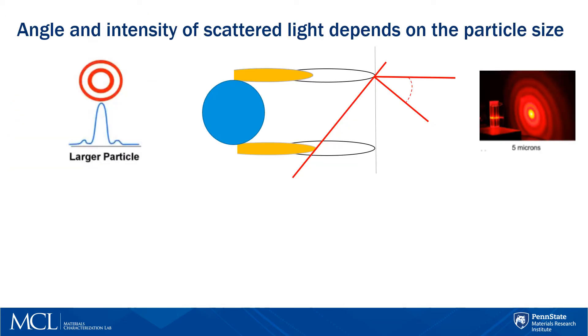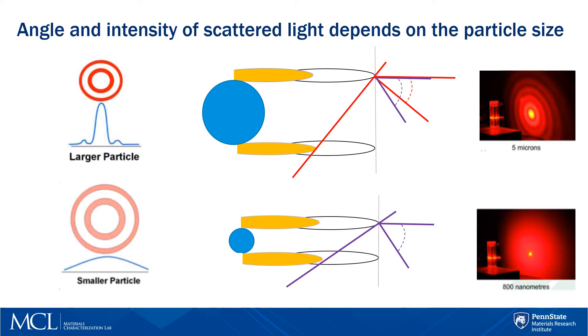We can do this because the angle and intensity of light depends on particle size. Larger particles scatter at more narrow angles but scatter light much more intensely. Smaller particles scatter over a wider range of angles but less intensely. So there is a fundamental relationship: the size of the particle is related to the angle of scattered light and also the intensity.